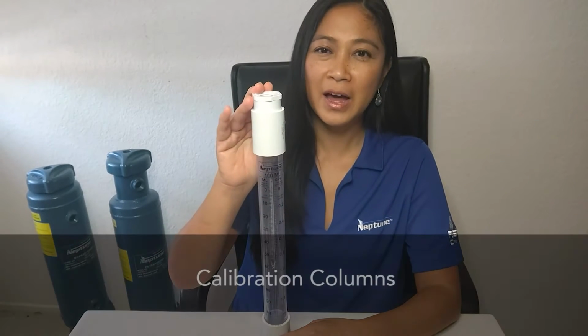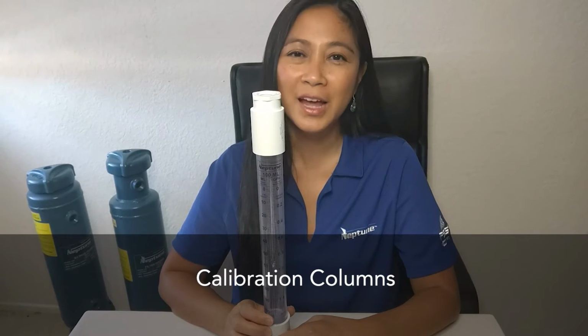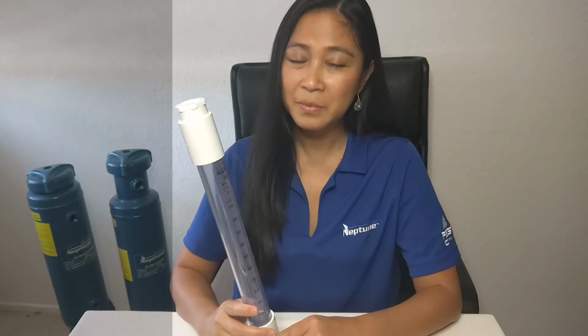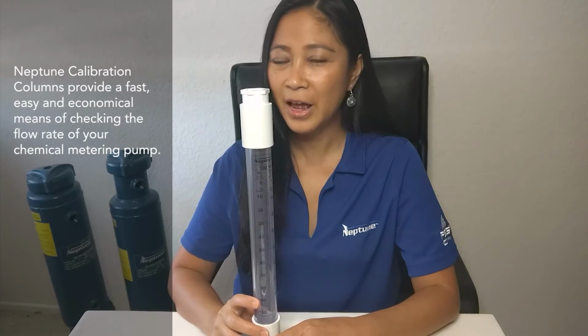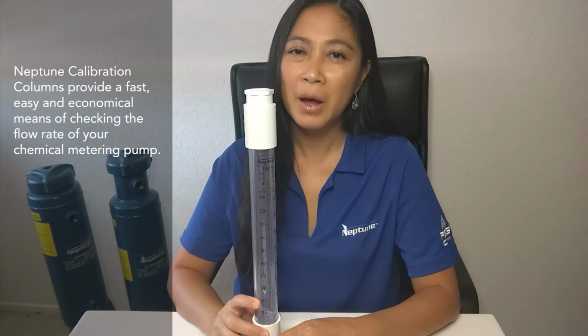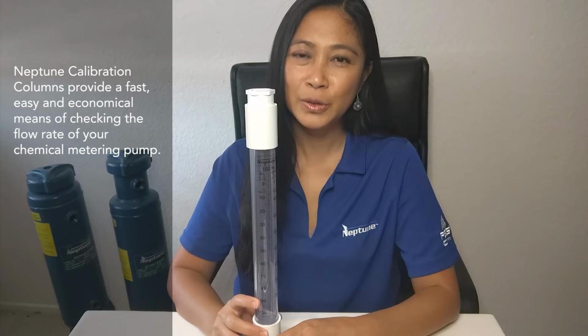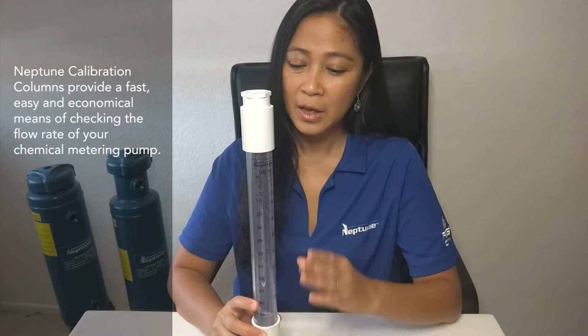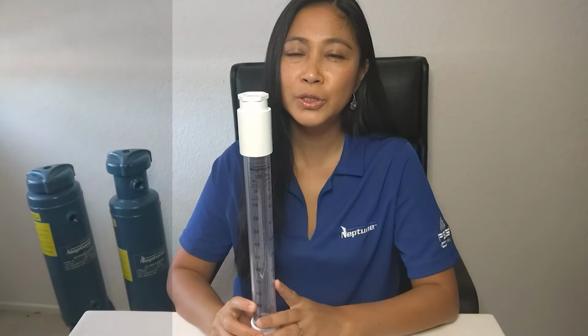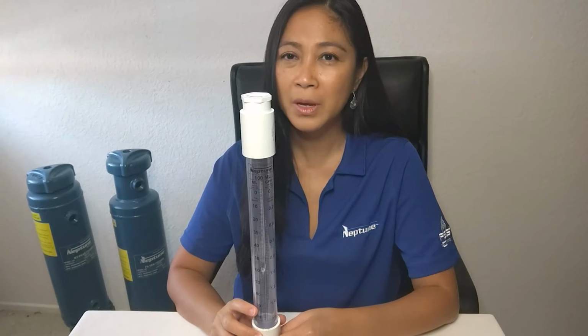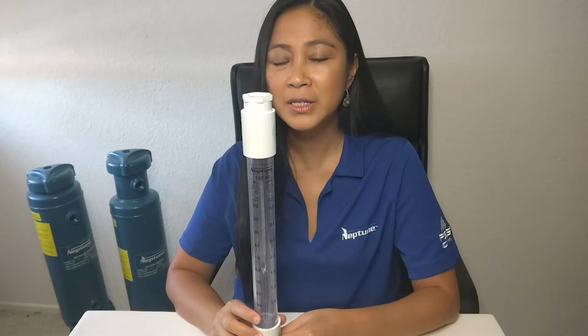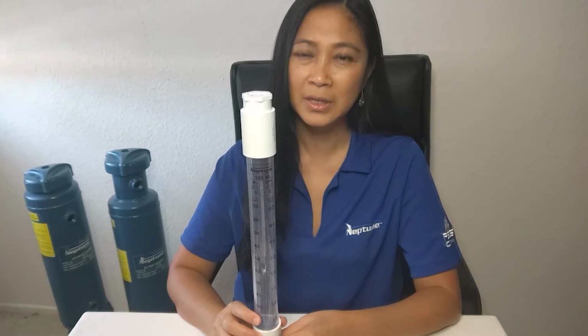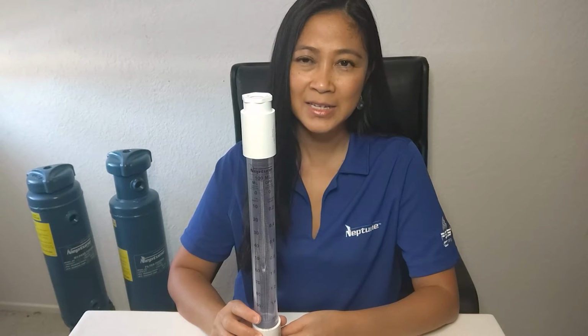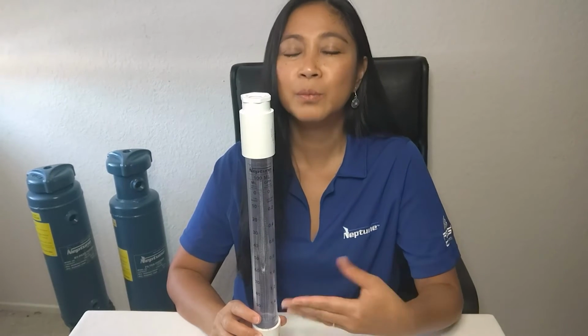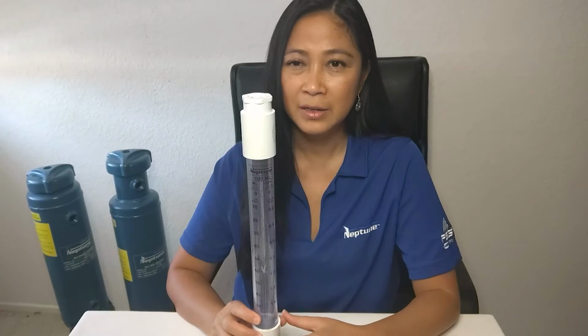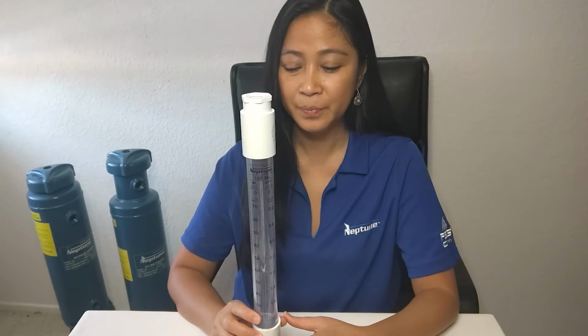Another accessory that I like to share its technical aspect is the calibration column. The calibration column is a convenient and accurate way to measure pump performance. It could also be used to troubleshoot your pump. When selecting a calibration column, be sure to select one so you could run a 1-minute or 2-minute test. For low flow pumps, you could run a 30-second test and multiply the result accordingly, whether it's a 1-minute or 2-minute test.